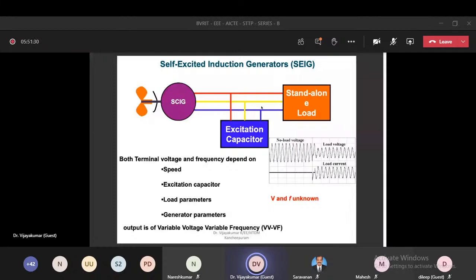Without the capacitor, if you connect only the load to the squirrel cage induction machine, this machine will not supply your loads. Even if you operate the machine above synchronous speed, you will not get any voltage at the terminals. Why? Because squirrel cage machines require the magnetizing current from the grid. Here there is no grid, no source available to provide the magnetizing current, so this machine will not induce any voltage. For that, we can come up with this topology. You can connect shunt capacitors at these terminals. These capacitors will provide the magnetizing current to the machine, so that you will get the induced voltage and frequency at the stator terminals. But what are the voltage and frequency? Because they are not matching the load and source.